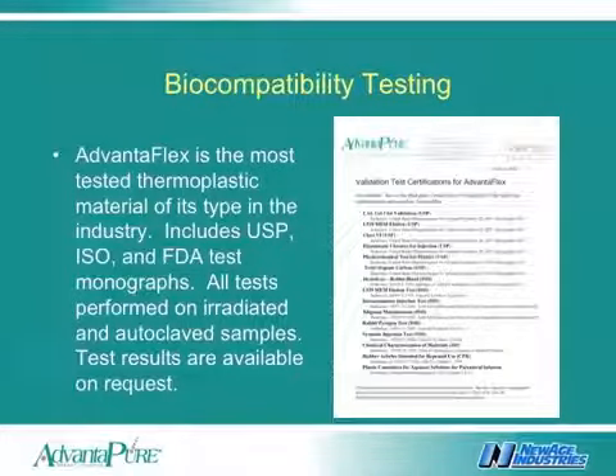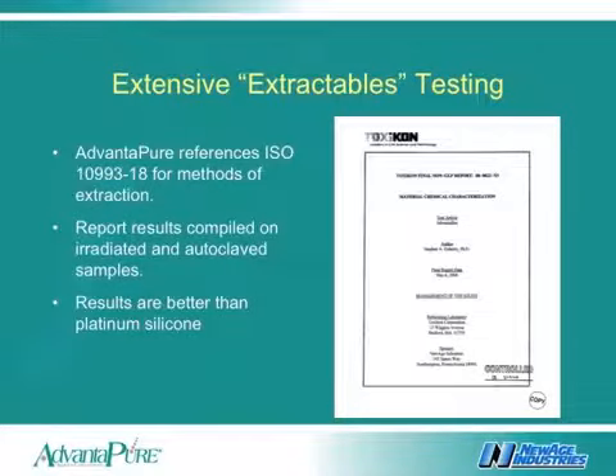This testing was performed on both irradiated and autoclave samples to provide test values using the condition that the tubing would actually be used. Additionally, extensive extractables testing results are also available using the analytical techniques referenced in ISO 10993-18. A close examination of these results will show values better than those of commonly used platinum silicones.